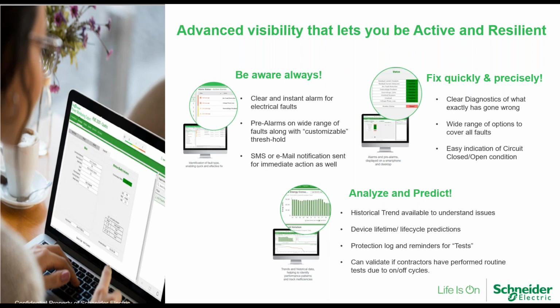So we can set pre-alarms to really become more proactive, and that allows, with the notifications, a new area that can mean we can offer service type contracts or service type offers to our customers. We can set it so that we can have SMS and email notification that can be sent for immediate action. It allows you to then be quick and precise to fix a problem. You know which circuit's got the problem, you know what type of problem is potentially about to occur, so that you're really sharp and laser pointed at the problem. When you get there, you know which distribution board, you know which circuit, you know the type of issue, you're well informed to make a quick and precise remedial action.